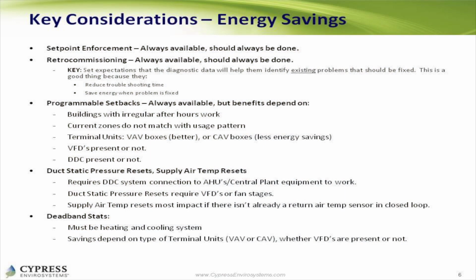So instead of the space being able to say, I'm going to go to 65, you can now control the range that set point will go. So now you can say, lowest you can go is 68 and the highest you can go is 72, or whatever the policy is in the building. But now you can set that parameter zone by zone. Retro commissioning savings, there's a lot of energy that is used to overcome poorly operating equipment. But often it's behind the walls or above the ceilings, and you don't really know it's not working properly. Well, now that you've got this data trended, you can start to see where equipment isn't working properly. So your retro commissioning, the savings from identifying those poorly operating equipment and making those repairs actually makes your building operate more efficiently. So you get kWh savings from that.